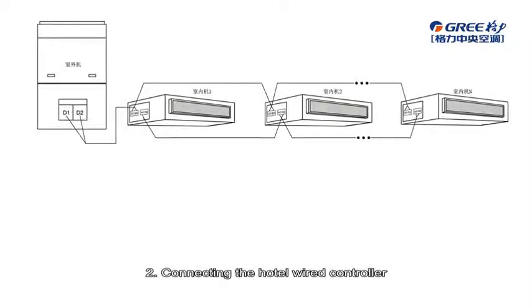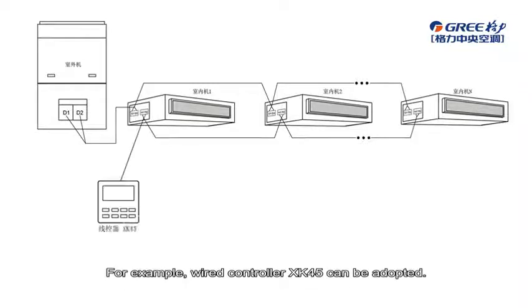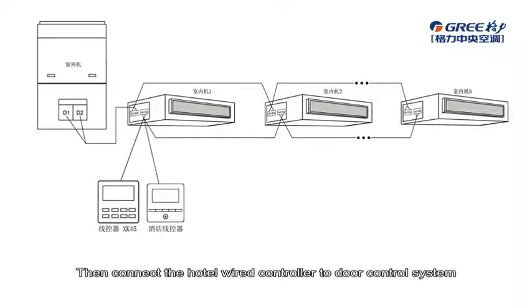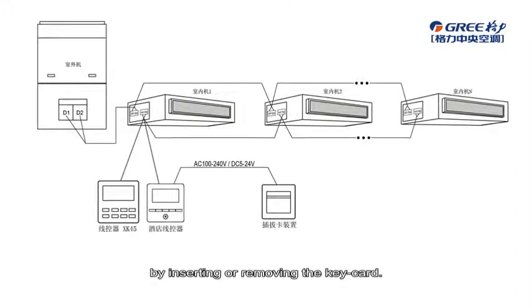Second, connecting the hotel wire controller with another wire controller. If the user needs door control system while he doesn't want to control the indoor unit only by hotel wire controller, another wire controller can be used together with hotel wire controller. For example, wire controller XK45 can be adopted. Set one wire controller as the master wire controller and set the other as the slave one. Then connect the hotel wire controller to door control system so that the unit can be turned on or off by inserting or removing the keycard.